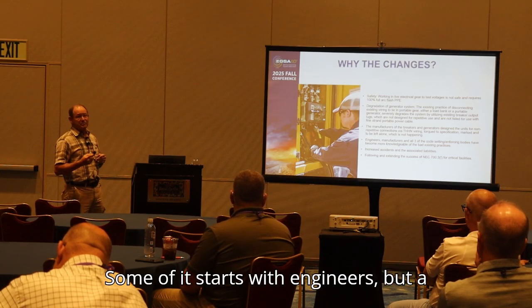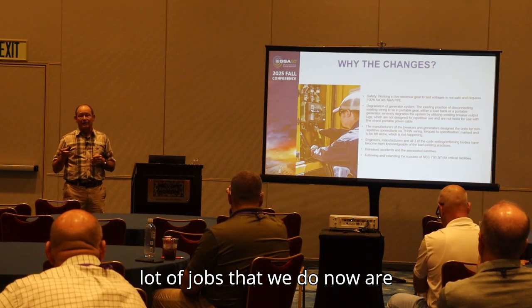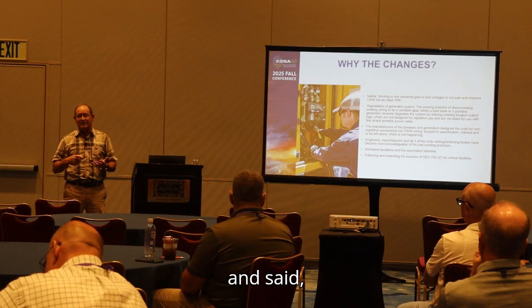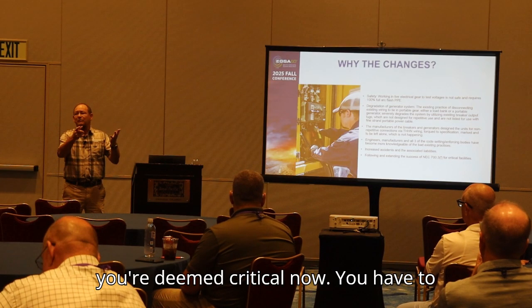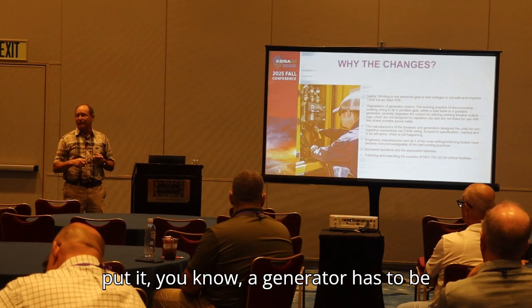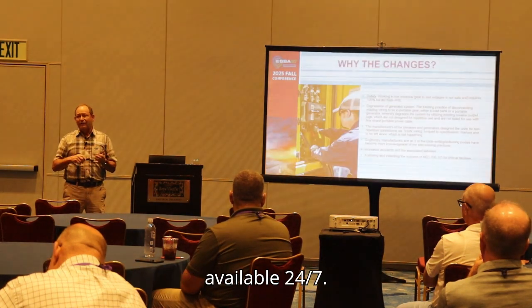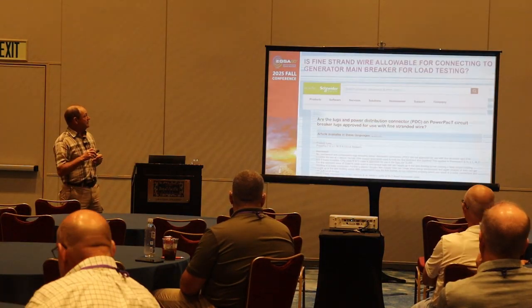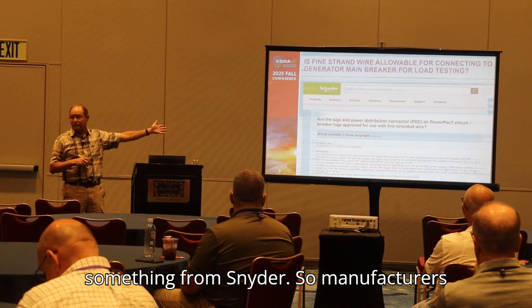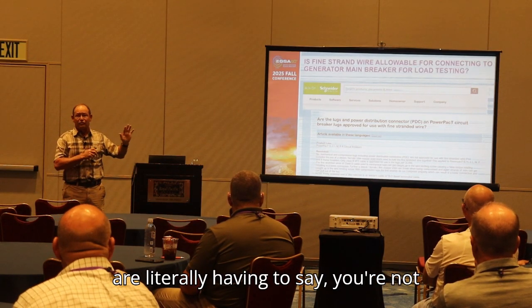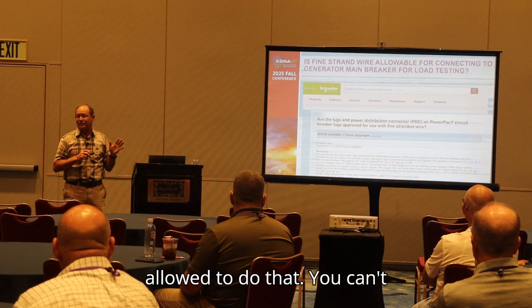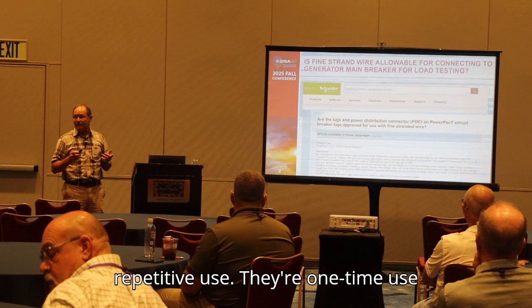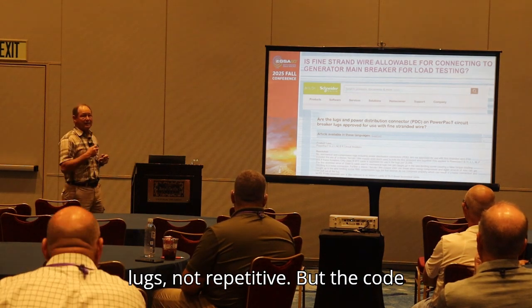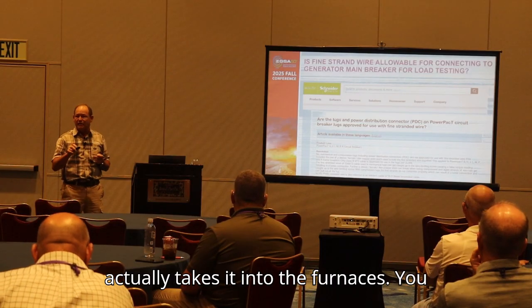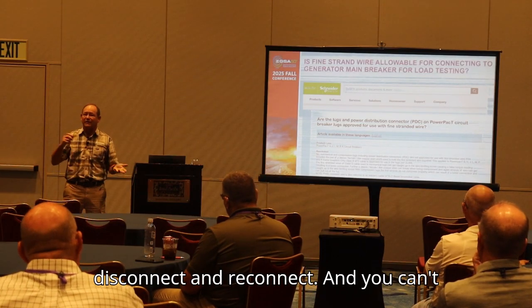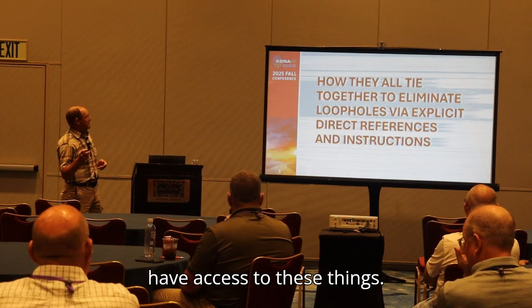Some of it starts with engineers, but a lot of jobs we do now are after the fact. The codes have come in and said you're deemed critical now. You have to put a generator that has to be full size, available 24/7. So manufacturers are literally having to say, you're not allowed to do that. They're one-time use lugs, not repetitive. But the code takes it further and says you can't alter the system, you can't disconnect and reconnect, and you can't have access to these things.